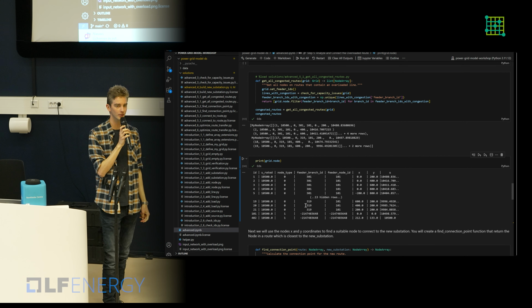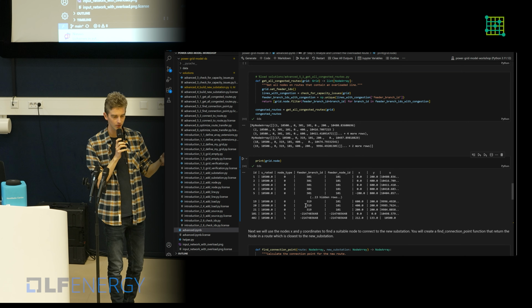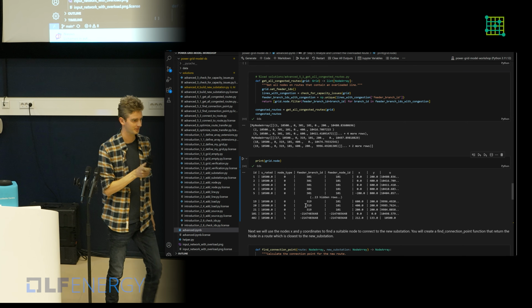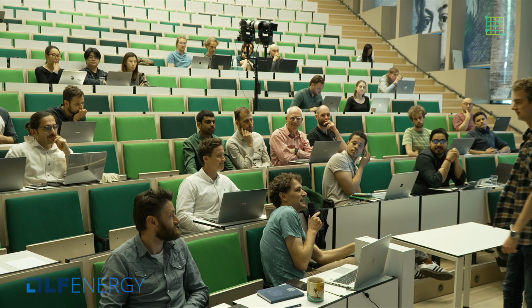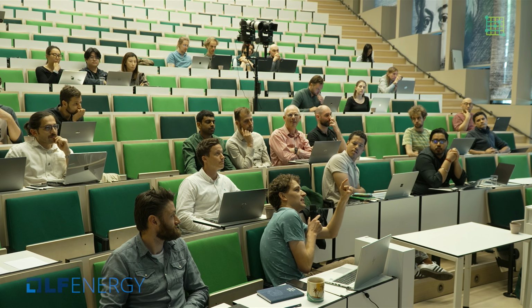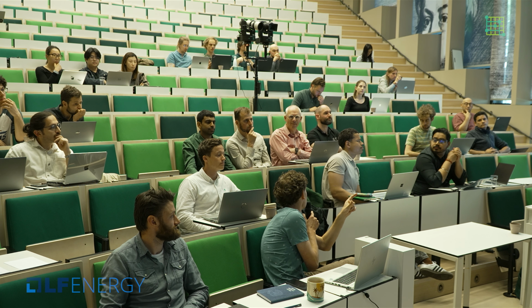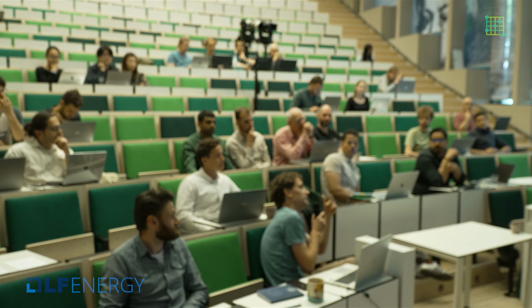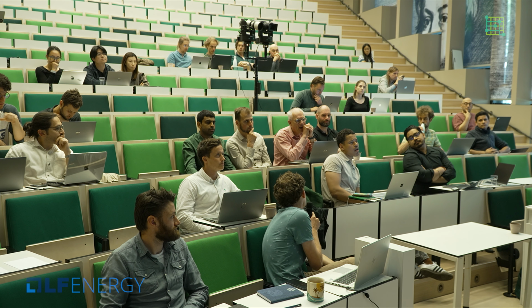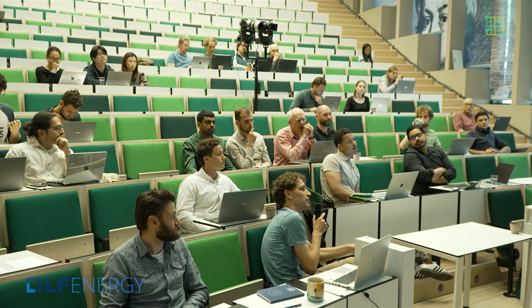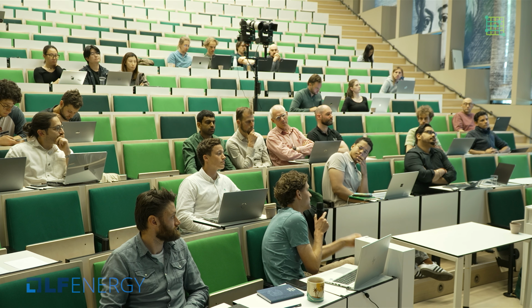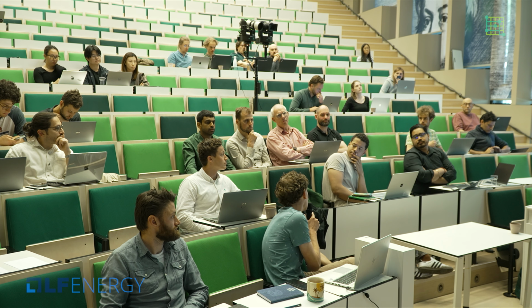So your question is, if you no longer have a radially operated grid, what happens to these IDs, Vincent? It picks one at random. It sees that there are 2 feeders in that route, and then it picks one at random. And you can either detect it by looking, are there 2 feeders with the same feeder branch ID? Then it's meshed, or detect cycles, which is also provided by Power Grid Model DS. So there's a cycles function which you can call to see which routes are cycles.